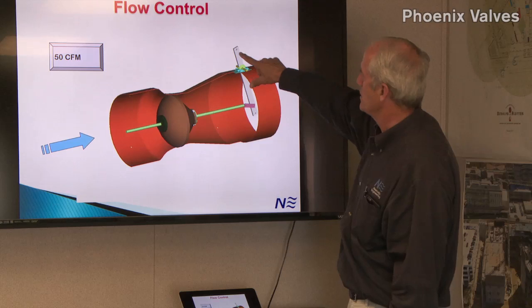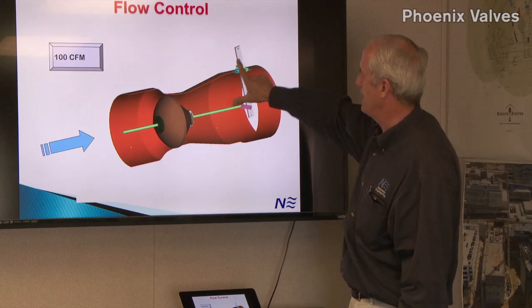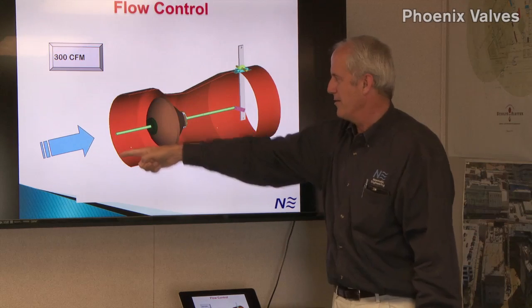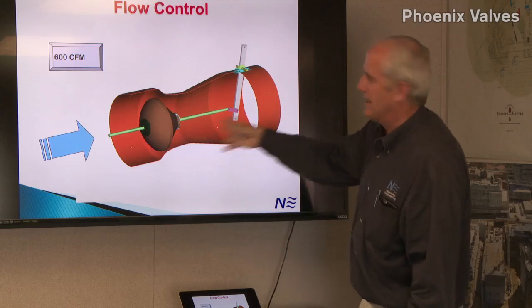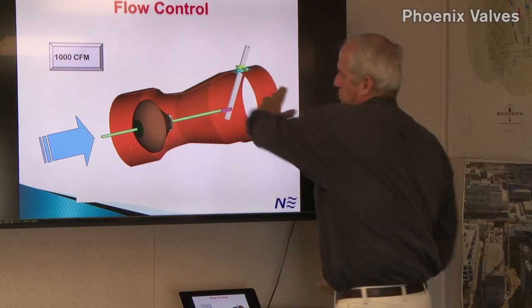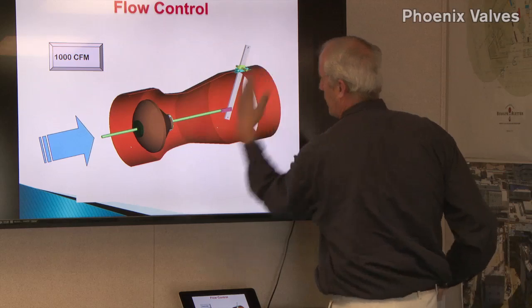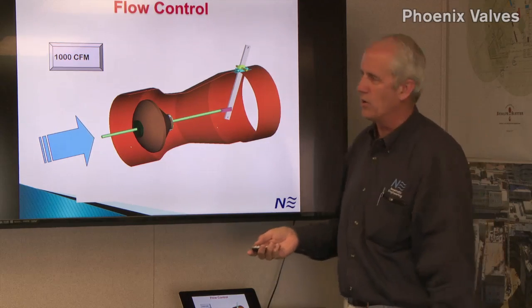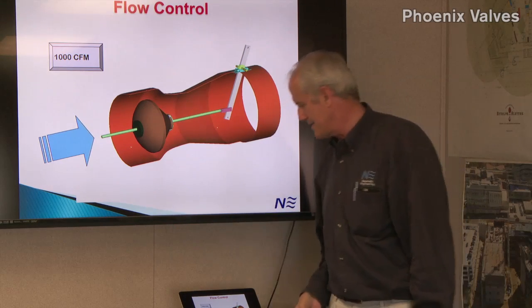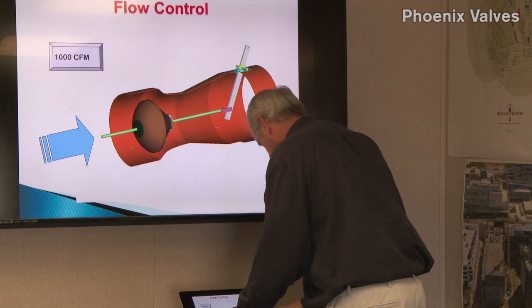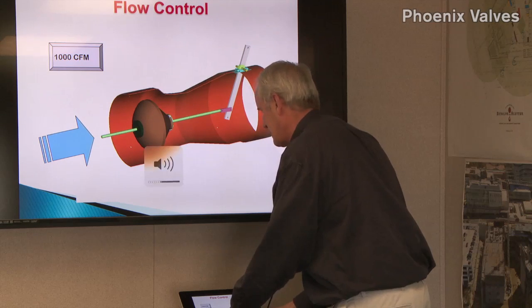All right, so for flow control, we just move our shaft. You move the shaft, you get more air, the arrow gets bigger. You get more air through the valve. Move the shaft this way, you get more air. Move the shaft that way, you get less air. Pretty simple the way it works. The pressure independence, we got a little movie here. I think the sound may work in this room. So it's going to show you how the pressure independence works.